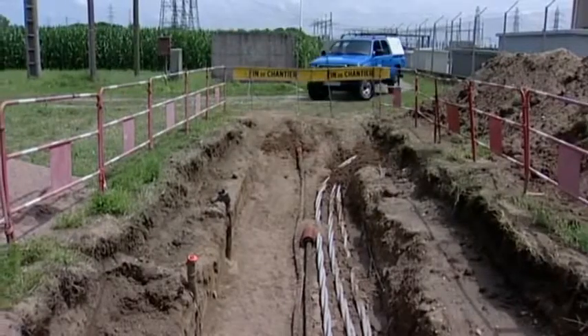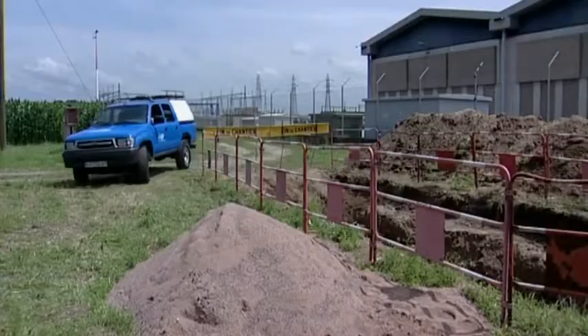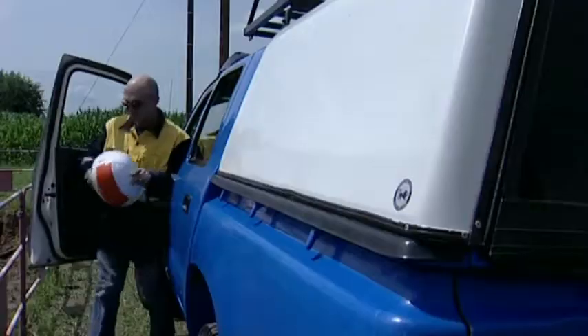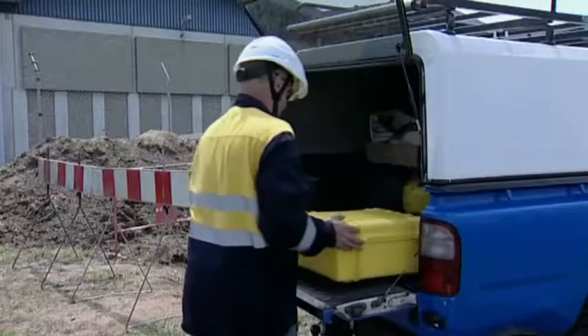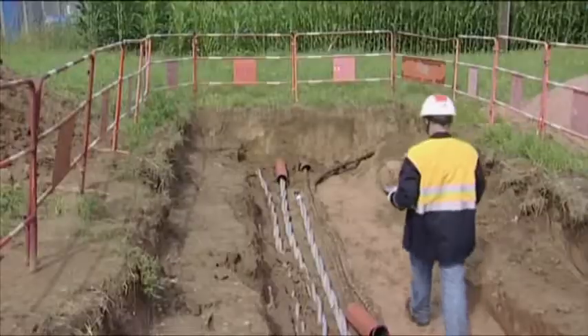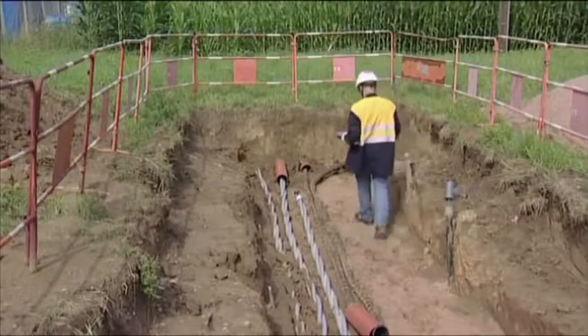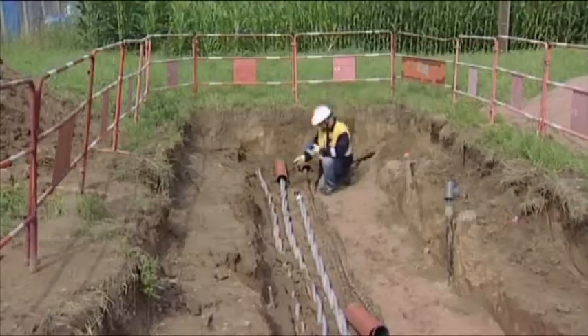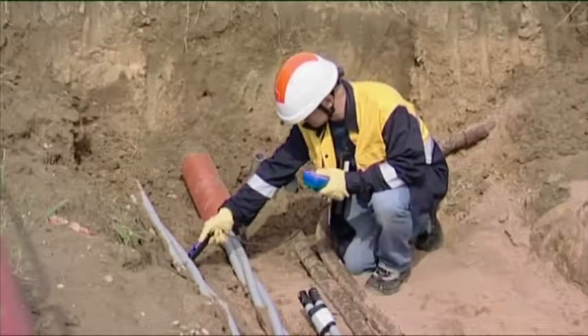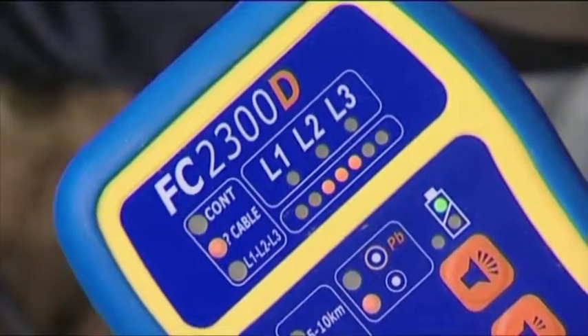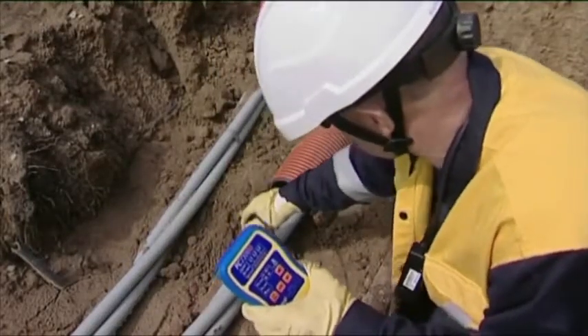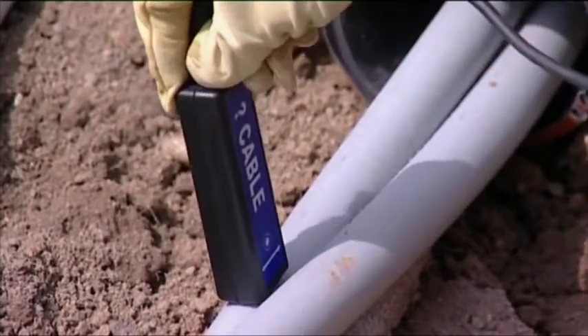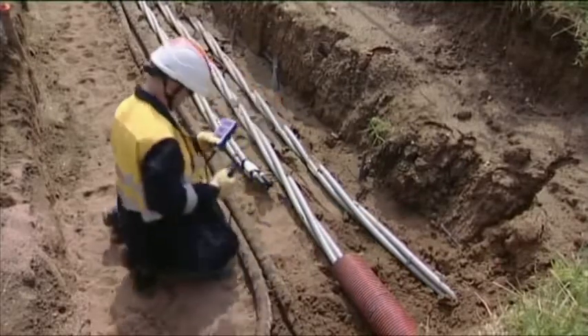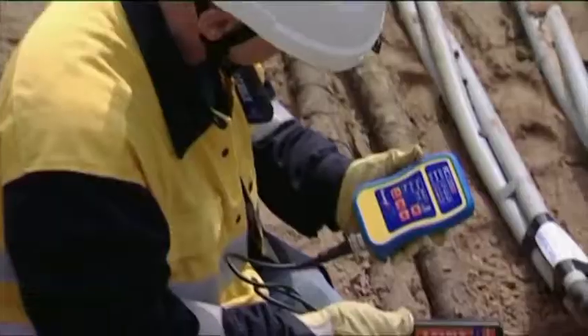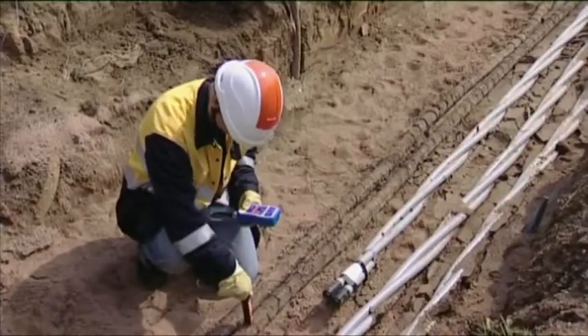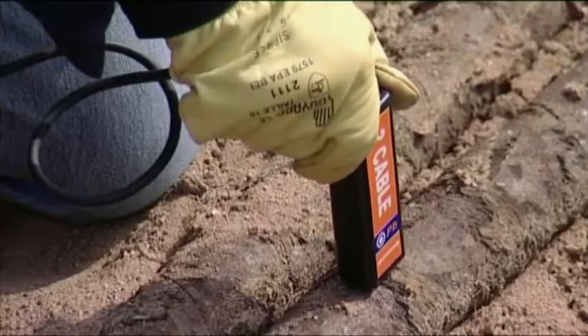Any electrician working on a network is aware that when underground, you can find numerous cables, and you can't make any mistakes, so you must check them all using the appropriate tester. Cutting the wrong wire means service interruption. This applies to electric power provided to customers as well as to telephone or cable network services. The blue probe is dedicated to electric cables with synthetic insulation. The orange probe is dedicated to oil paper insulated cables, lead sheathed cables and steel reinforced cables.